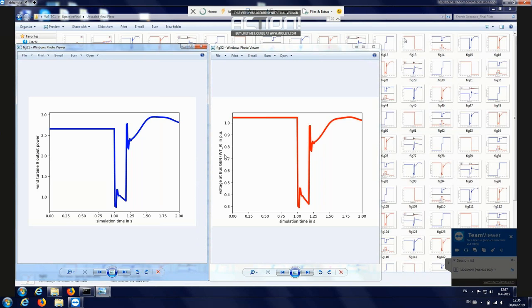Then at the instant of 1 second, there was a fault. The voltage dips considerably, then the controller reactive power support comes into play and boosts the voltage. Slowly and steadily, we move back to the voltage we need, which is around 1 PU. As you can see, the pattern is almost the same for both the output power and the voltage.